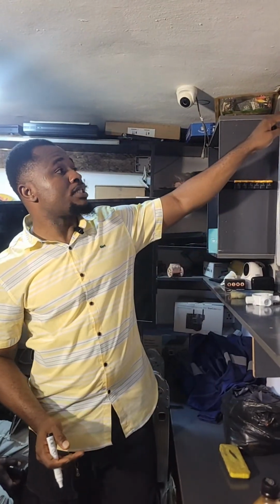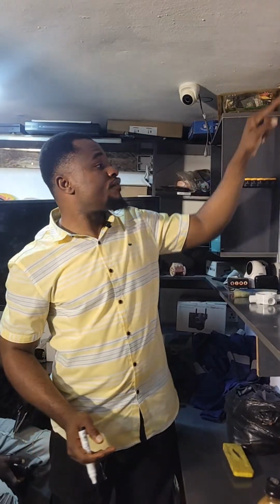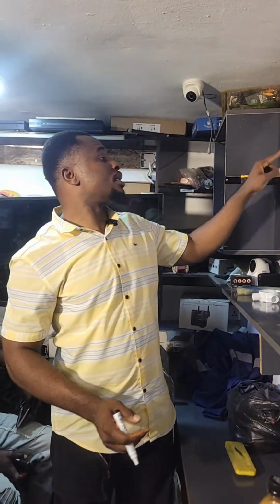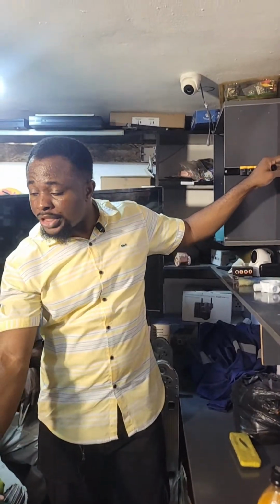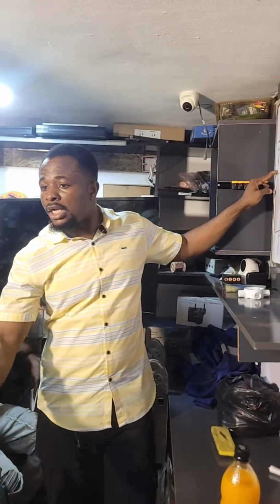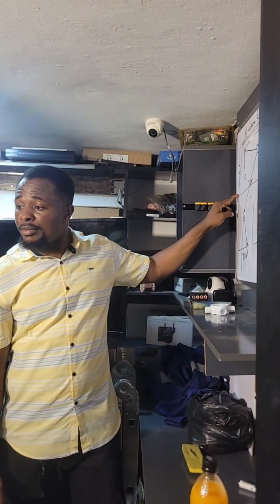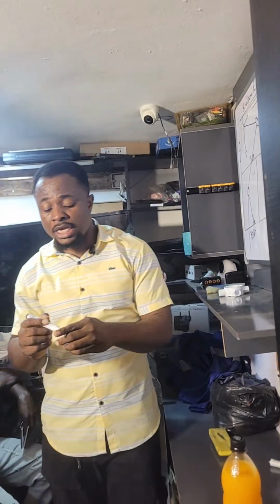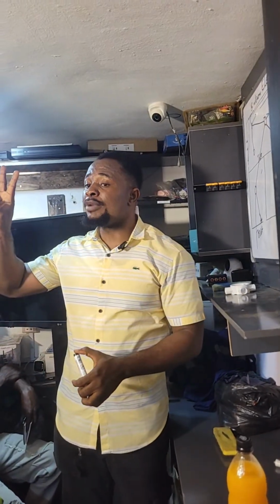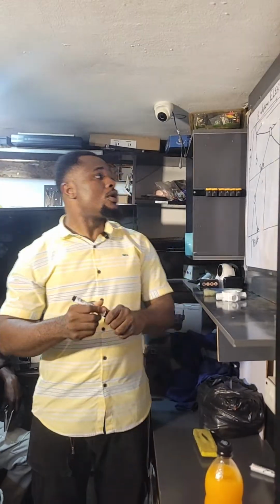Because we already have bed socket here, we already have wardrobe here, we already have TV socket here. So the next place we can put a socket is this point. Reading table, this point. Extractor, standing fan, this point. Am I communicating? So most of the time we should try in our head to create 3 sockets in every bedroom.